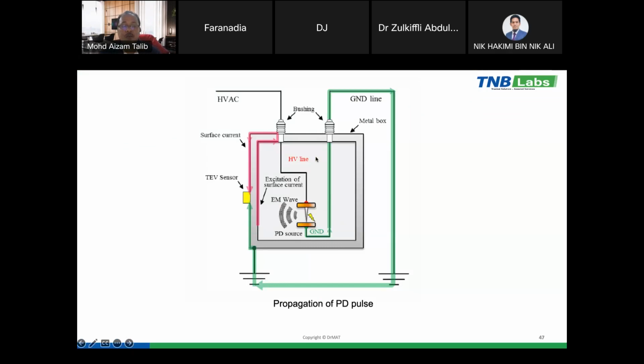So here is a more detailed explanation of the TEV. When a partial discharge occurs, it will generate an electromagnetic wave or electromagnetic signal. When this electromagnetic wave hits the surface of the conductor or the metal, it will create a current spike, and this current spike will travel along the surface of the conductor. When we provide a gap, this current spike will travel to the outer surface of the equipment, and when we use the TEV sensor, we are able to pick up this current spike.